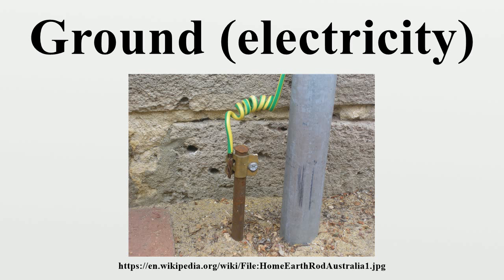Building wiring installations. Electrical power distribution systems are often connected to ground to limit the voltage that can appear on distribution circuits. A distribution system insulated from ground may attain a high potential due to transient voltages caused by arcing, static electricity, or accidental contact with higher potential circuits. A ground connection of the system dissipates such potentials and limits the rise in voltage of the grounded system.